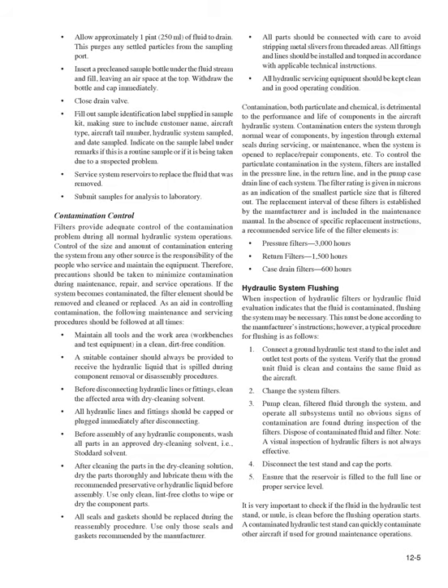In the absence of specific replacement instructions, a recommended service life of the filter elements is: pressure filters, 3,000 hours; return filters, 1,500 hours; case drain filters, 600 hours. Hydraulic system flushing: when inspection of hydraulic filters or hydraulic fluid evaluation indicates that the fluid is contaminated, flushing the system may be necessary. This must be done according to the manufacturer's instructions. However, a typical procedure for flushing is as follows.